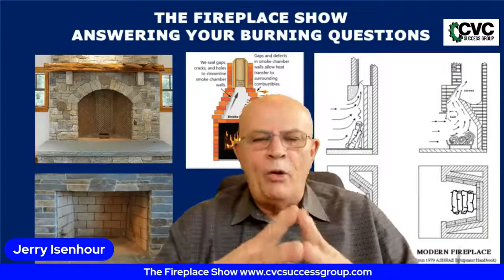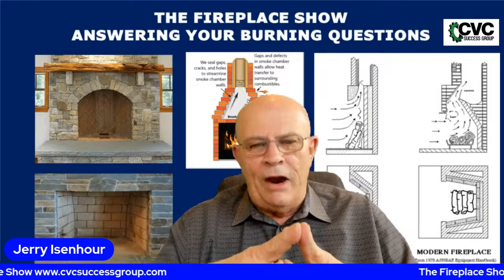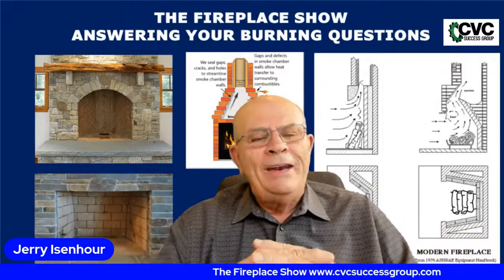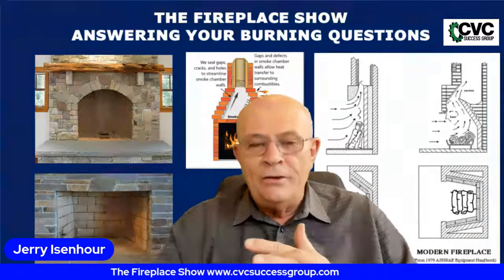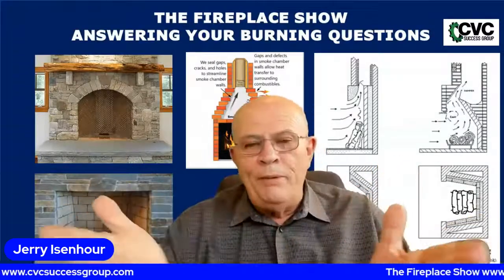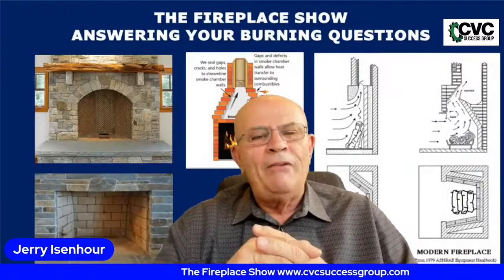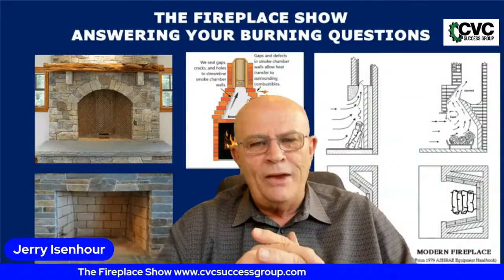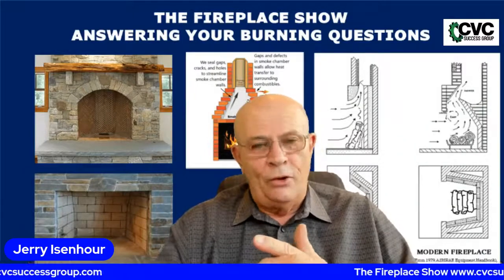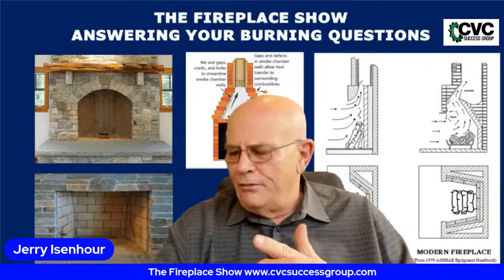Now, let me go over a couple more problems that we're commonly finding in the field with open wood burning fireplaces. And there are products that can take care of this. One is we're finding a lot of fireplaces that right under that fire brick, they have built wood. That's correct. There was a form built in and the brick is laying on top of it. And this is now being traced to a lot of house fires because that wood goes through a process called pyrolysis and also called vaporization, where it can catch on fire at some time down the road. So again, these are various issues.